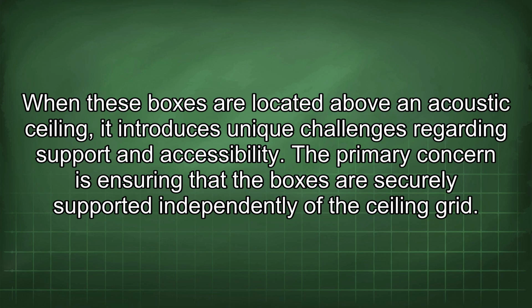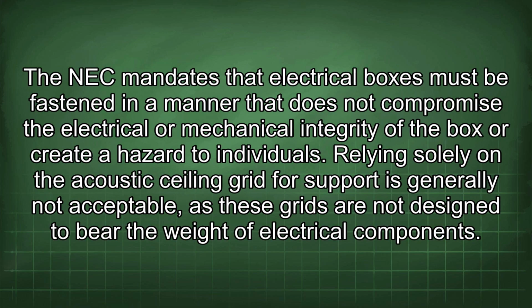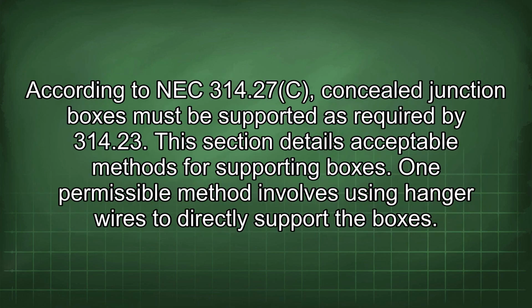The primary concern is ensuring that the boxes are securely supported independently of the ceiling grid. The NEC mandates that electrical boxes must be fastened in a manner that does not compromise the electrical or mechanical integrity of the box or create a hazard to individuals. Relying solely on the acoustic ceiling grid for support is generally not acceptable, as these grids are not designed to bear the weight of electrical components. According to NEC 314.27(c), concealed junction boxes must be supported as required by 314.23. This section details acceptable methods for supporting boxes.